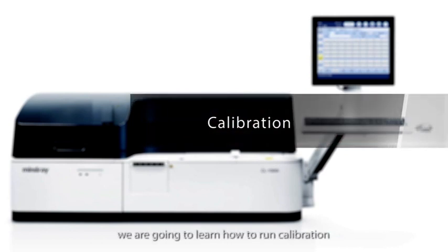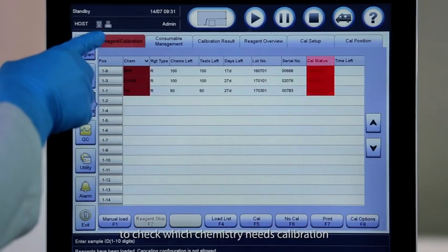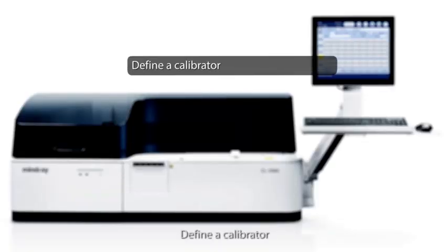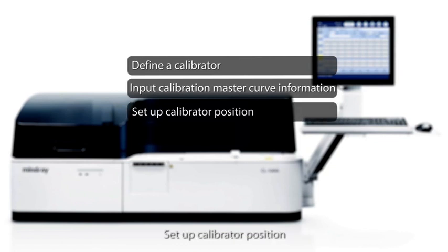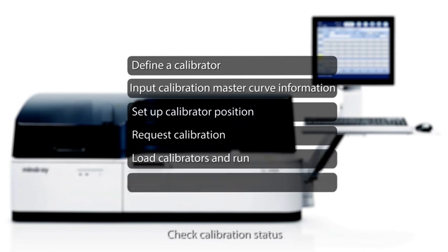Moving on, we are going to learn how to run calibration. You can go to the reagent calibration page to check which chemistry needs calibration. If you run a calibration, you can perform in the following order: Define a calibrator, input calibration master curve information, set up calibrator position, request calibration, load calibrators and run, and check calibration status.